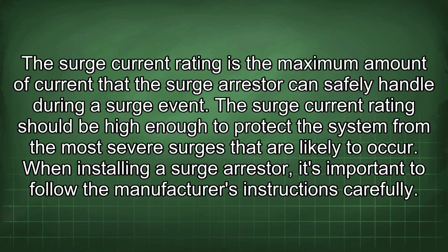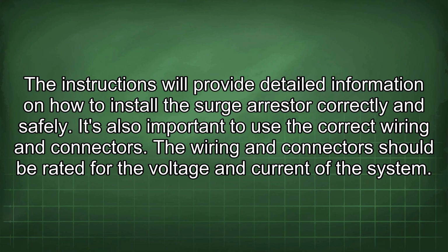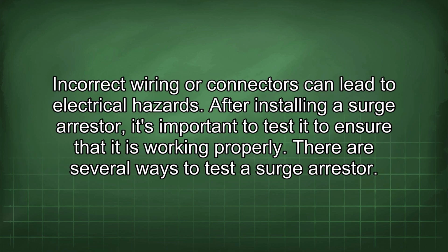likely to occur. When installing a surge arrestor, it's important to follow the manufacturer's instructions carefully. The instructions will provide detailed information on how to install the surge arrestor correctly and safely. It's also important to use the correct wiring and connectors. The wiring and connectors should be rated for the voltage and current of the system. Incorrect wiring or connectors can lead to electrical hazards.